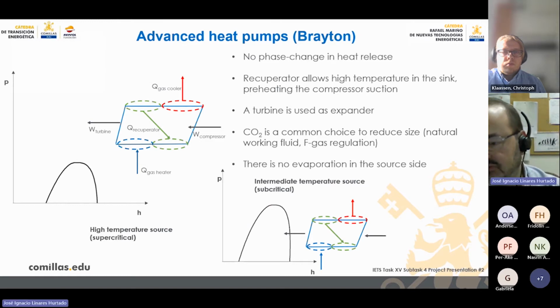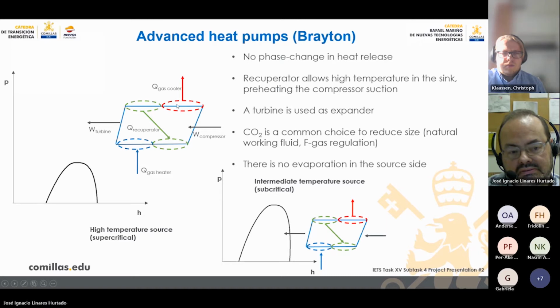And finally, this is our proposal for the heat pumps. We can design an advanced heat pump based on the reverse Brayton cycle. Okay, we are using a Brayton cycle, that is, a cycle with gas, not with a pure substance which can have phase change, but working as a gas. So there is no phase change in the heat release in this zone, and no evaporator on the source side, because we are far away from the dome. Again, a recuperator here allows that high temperature in the sink, and at the same time we are preheating the compression suction, so we obtain a high temperature here. This is the effect of the recuperator, and we have removed the valve for the expansion, replacing it with a turbine or an expander.